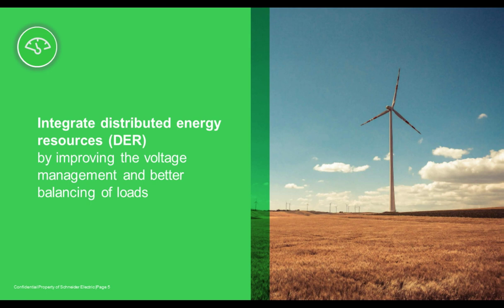On the other hand, one of the main responsibilities around the world is to maintain voltage fluctuation within limits as contractually agreed and requested in network codes. The voltage control has traditionally been performed by transformers using on-load tap changers and capacitor banks that inject reactive power into the grid and are located at the high voltage, medium voltage substation level. The distribution system operator fixes a set point and prepares a scenario and range based on forecasted load and production curves, for example. As a result of the massive integration of distributed energy resources into the medium voltage, low voltage grid, voltage management today presents a major challenge.